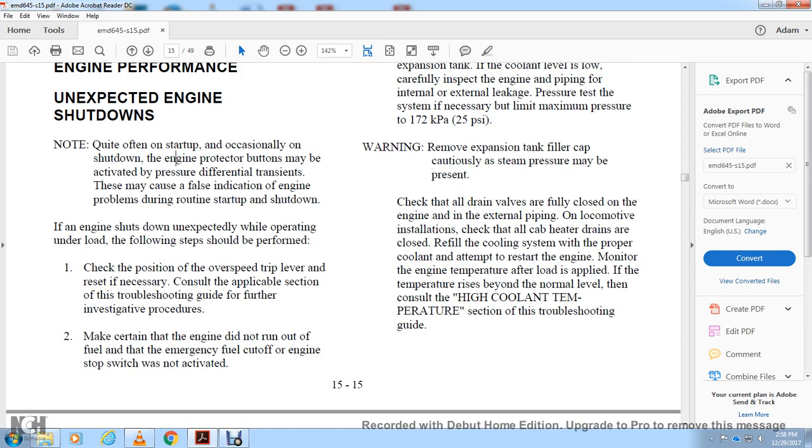Check all cab heater drains are closed before refilling the cooling system. Monitor engine temperature after load is applied. If temperature rises above normal levels, consult the high coolant temperature section of the troubleshooting guide.